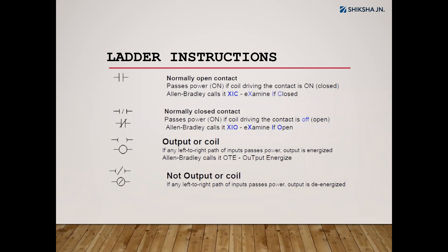In ladder programming there are instructions — you can assume them as commands. The basic commands used cover almost 80 to 85 percent of programming, and they consist of only three symbols. The first one is the normally open contact. You can see this symbol on the left-hand side. Assume it as an open switch — by default it has no connection, and when the switch is closed it allows the supply through. That is the normally open contact.